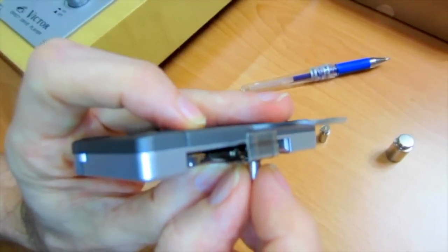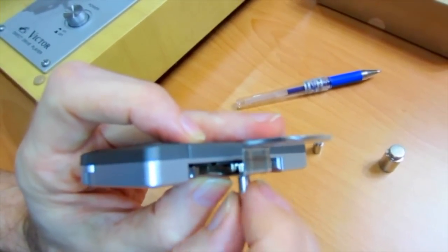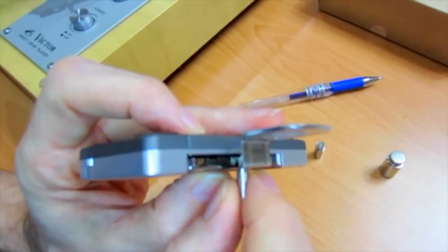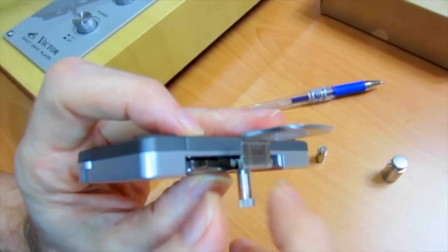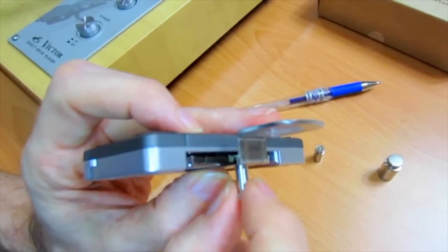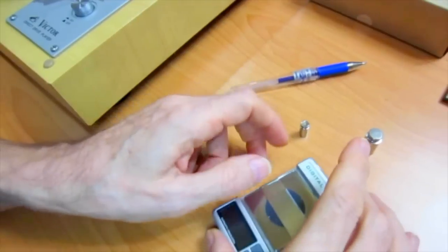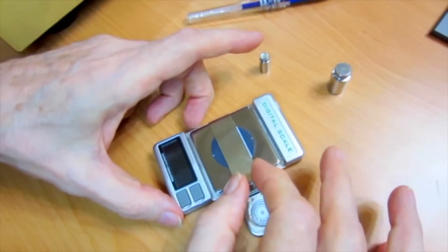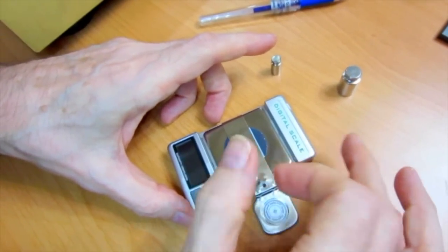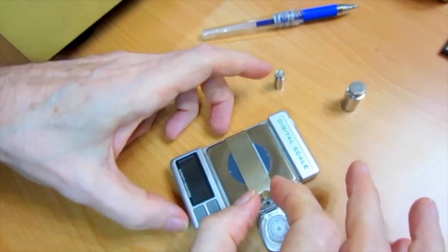And again, what I'm doing is this tab goes into the central slot on this side, and very gently tighten it. You don't need any torque at all, just very gently. A 5 gram mass isn't going to have any influence, this isn't going to move around. So again, don't over tighten because you may damage the sensor, just very gently.